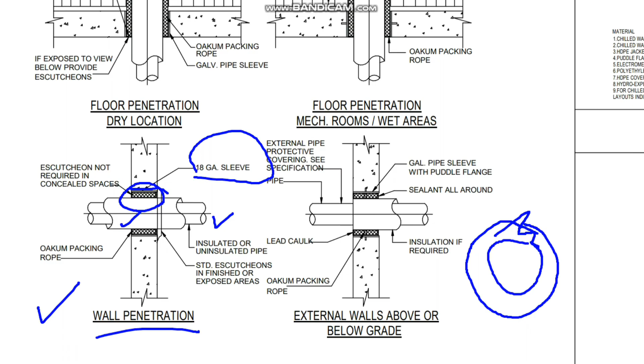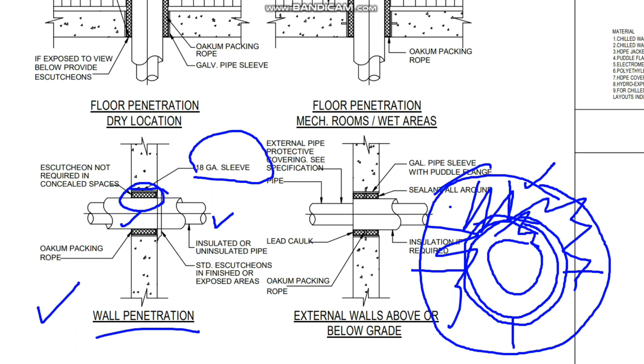For example, if this outer area is 150mm, that means the GI sleeve must be at least 200mm. Now coming to the mechanical or HVAC engineer's scope of work, this gap between the sleeve and the pipe has to be filled by the mechanical or HVAC engineer. Normally we can provide fire sealant or material like Oakum packing rope to seal the gap, as shown here.